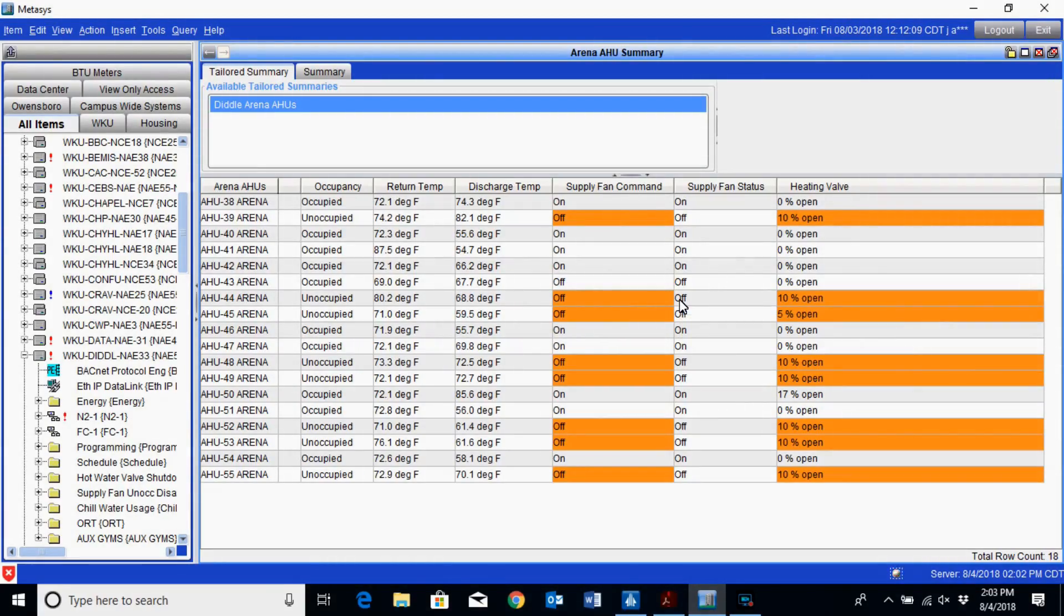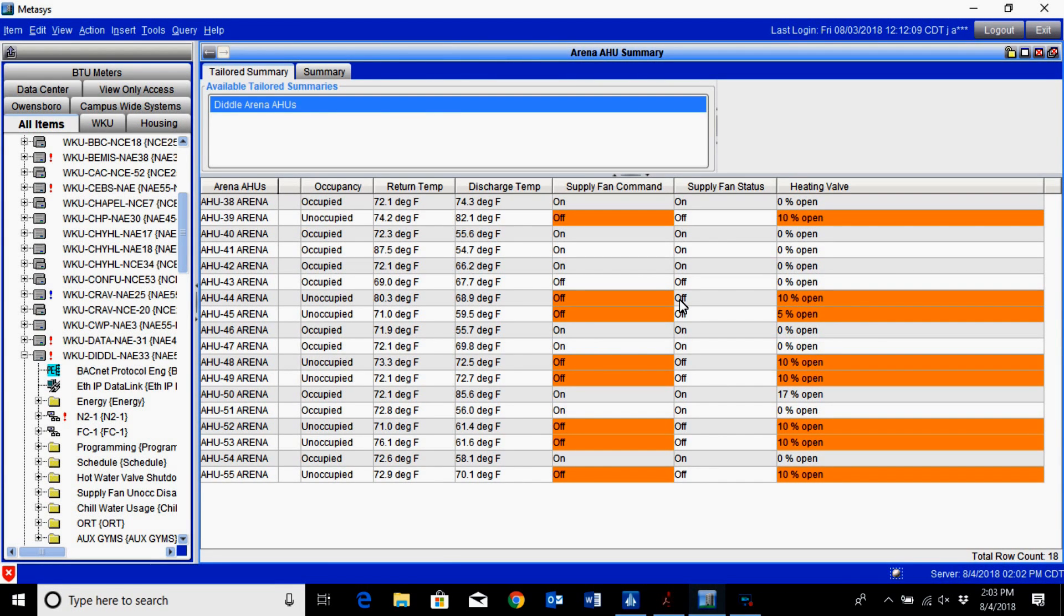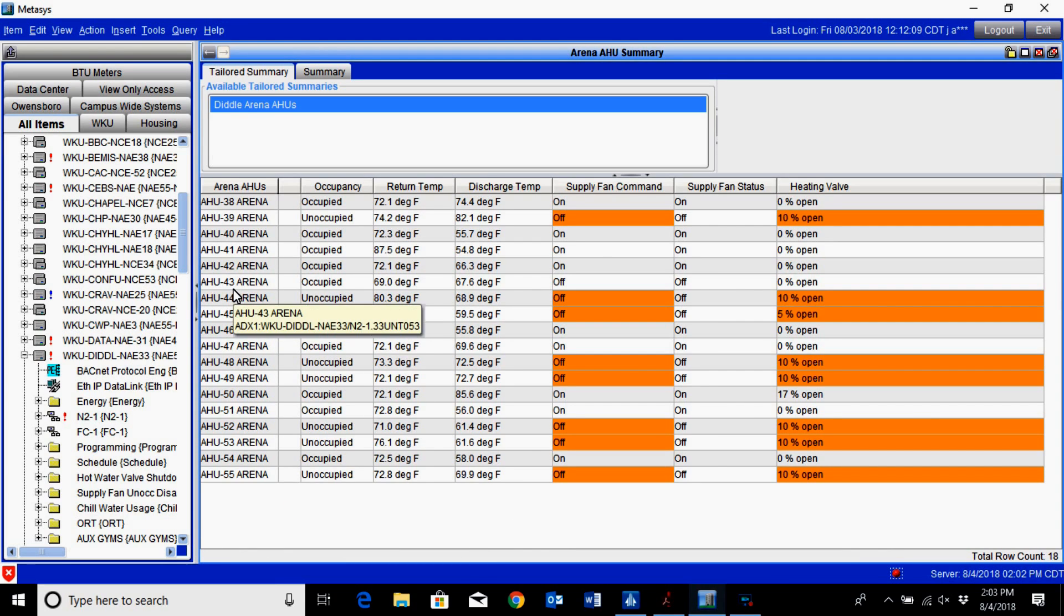In this video we are going to be talking about how you can use a single schedule to stage on multiple air handlers. It's actually using a combination of a schedule and an interlock to bring on several units without having to have multiple schedules, a situation where you may need to do this is in a building with multiple air handlers.